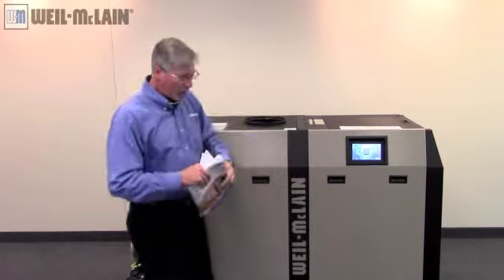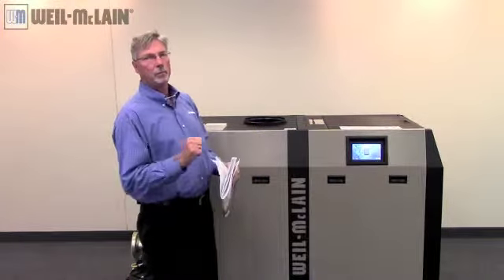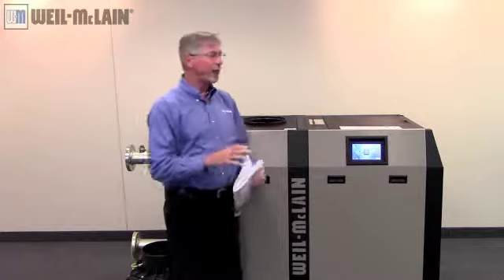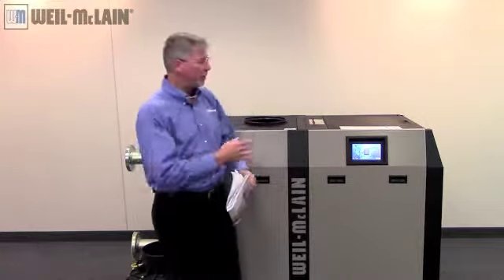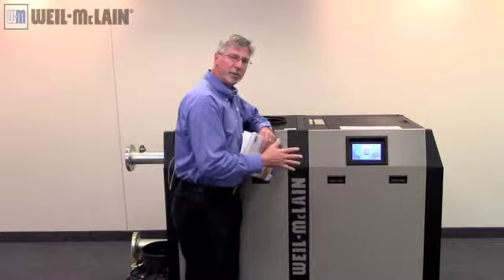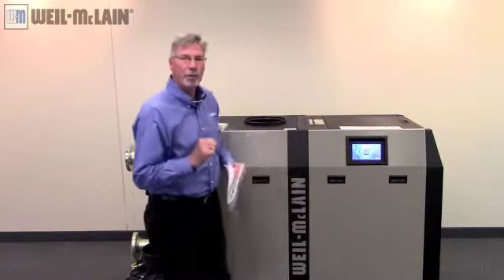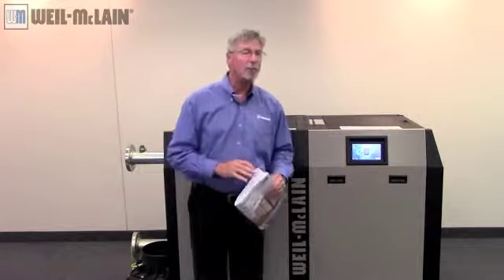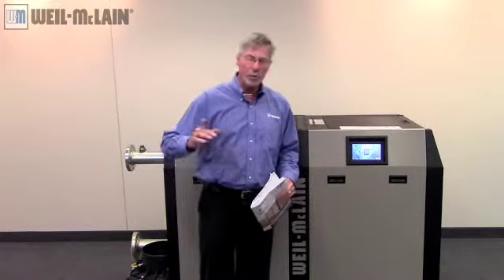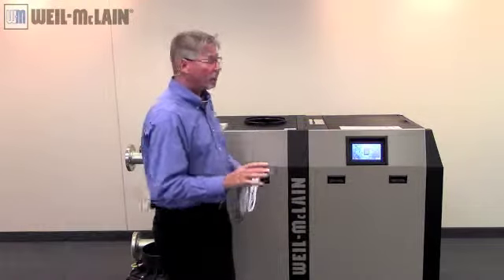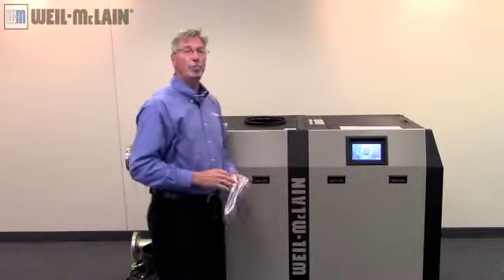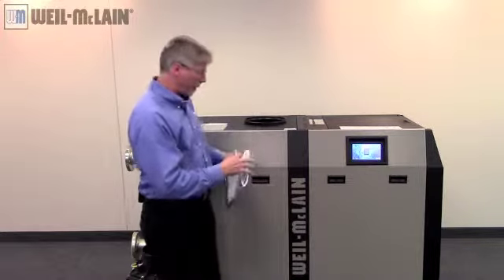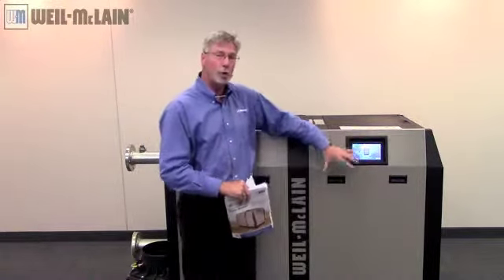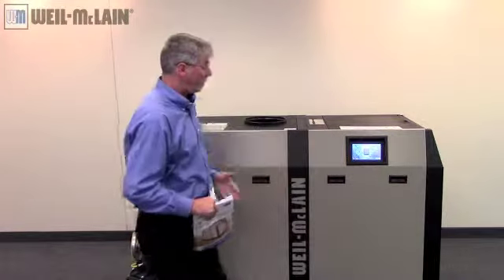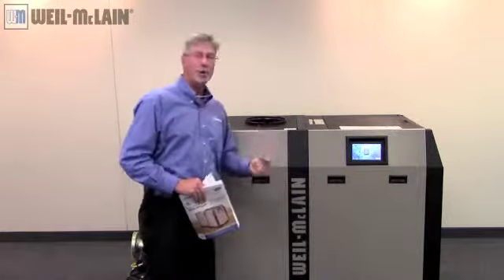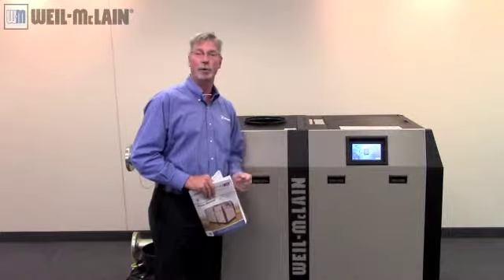Now, the majority of the problems that I've seen with a new installation usually has to do with high temperature switches. Somehow we've gone off on limits, high temperature limits, and nobody knows what the problem is. Well, in almost every case that I've walked up to, the problem has to do with flow on a new installation. Somehow we're not moving enough water through this boiler to get the heat off. Now remember, you're talking anywhere between 1 million, 1.5, or 2 million BTUs. And if you don't move this water through this heat exchanger, it overheats like that, and this will shut down and lock out on you right away.